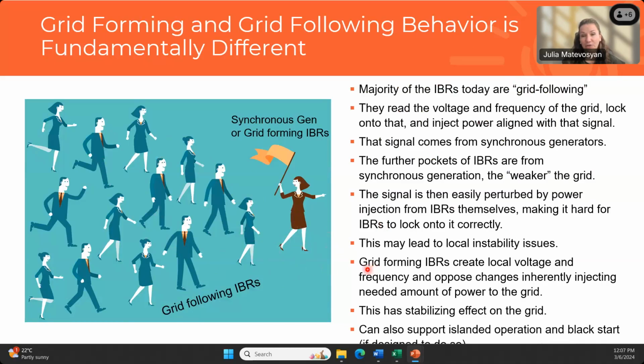So majority of inverter-based resources today are grid following. They read voltage and frequency of the grid, and then they lock onto that and inject power aligned with that grid signal. And that grid signal today comes from conventional synchronous generators. It just kind of by the way the grid was designed and by the way synchronous generators were designed over time. The further the pockets of inverter-based resources are from synchronous generators, the weaker the grid.